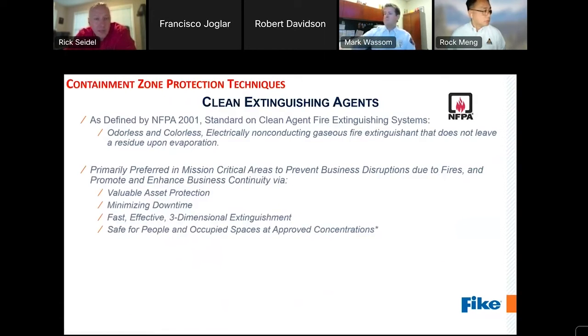One such option that we may see on these units is a clean agent system. Clean extinguishing agent systems do remain extremely popular in many mission critical and high value asset areas, as they are extremely effective at quickly and cleanly extinguishing class A, B, and C fires, and they're safe for occupiable areas at approved concentrations. But when it comes to discharging a clean agent system in an energy storage enclosure, it depends on when and how you plan to detect and discharge the system to determine its utmost effectiveness or level of protection. Next, please.